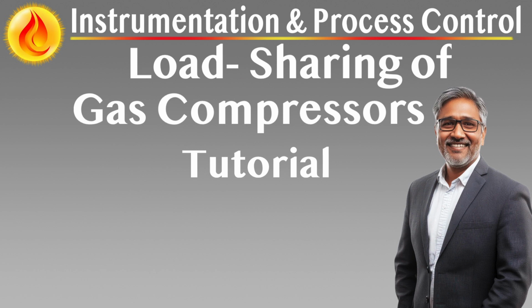Functional role in compressor control. When a compressor train enters a condition where recycling cannot be avoided, each anti-surge controller monitors the valve position and rate of change of its counterparts. Based on this shared intelligence, controllers adjust their own outputs to align with the behavior of the group. Two primary operating conditions are handled distinctly.